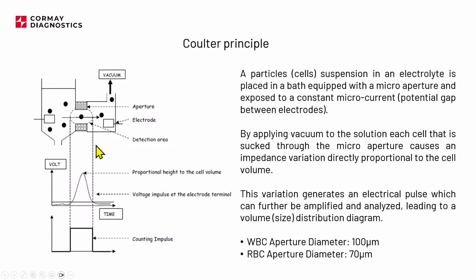So when you consider the cell as a particle, you know that the cell has a membrane, right? And on the surface of this membrane, we have lipid layers. One side of this layer is hydrophobic, and the other is hydrophilic. What else is important here is that this lipid layer doesn't conduct any electricity, right? This is one of the properties of this lipid layer. So you can consider those cells as small particles which are not conducting electricity. And since the Coulter principle relies on the impedance change in this small region which we call the aperture, when the cell is passing through the aperture, we can detect such a change of impedance.